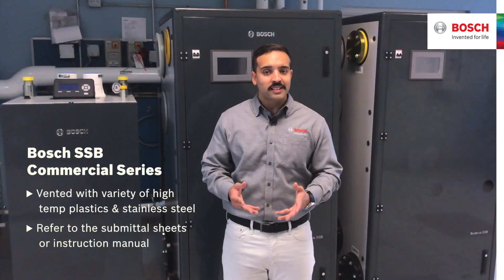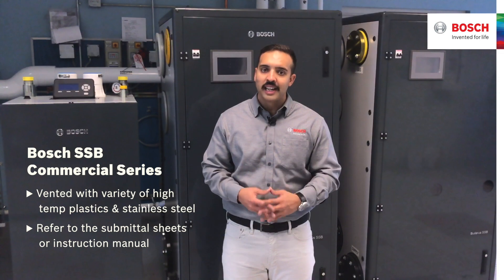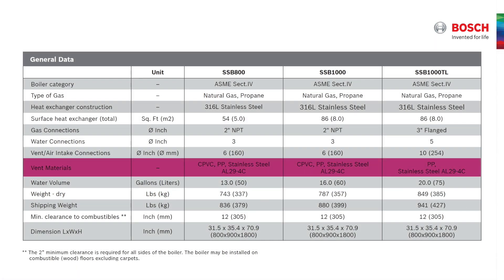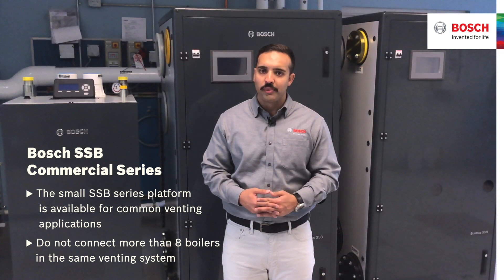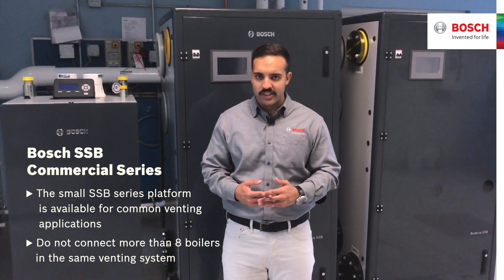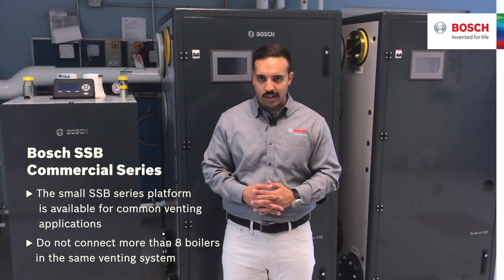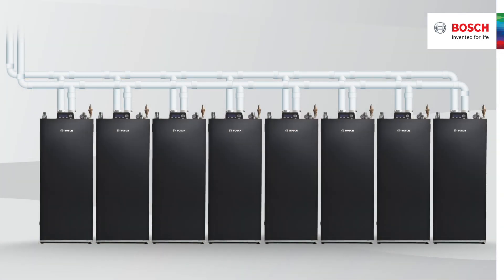The whole product range is designed to be vented with a variety of high-temperature plastics and stainless steel. Refer to the submittal sheets or instruction manual to see what materials are acceptable for the boiler you select. The small SSB series platform is available for common venting applications, reducing the number of penetrations of the building envelope. It is recommended that you do not connect more than eight boilers in the same venting system.